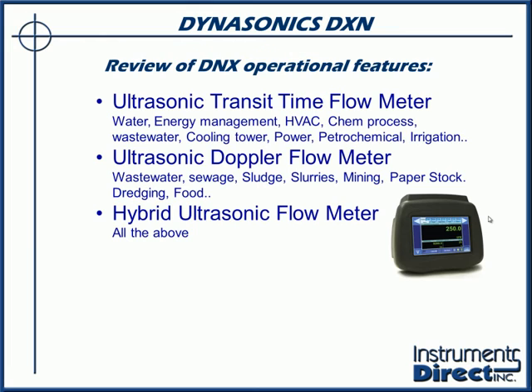So what we've done is we've put both of those theories of operation in one box. If we break this down, the ultrasonic transit time flow meter is designed to work primarily for your cleaner liquid applications. So it's going to work in your water, any aqueous application, energy management, HVAC, chemical process, wastewater, cooling tower, power, petrochemical, irrigation, and the list goes on. If you have a closed full pipe that doesn't have chunks of stuff in it, then the ultrasonic transit time technology is probably your application.